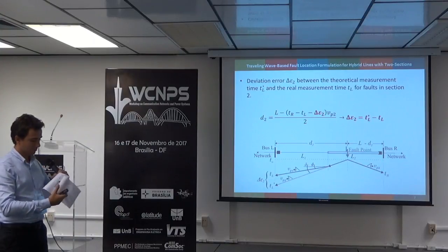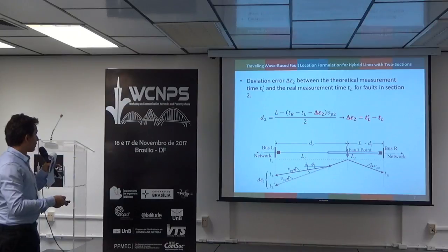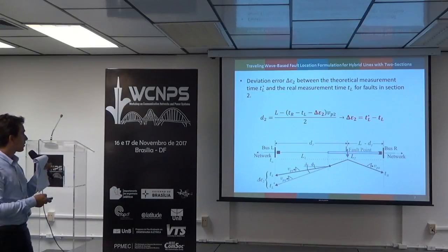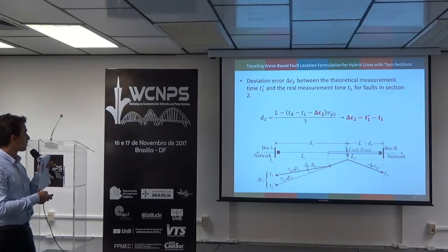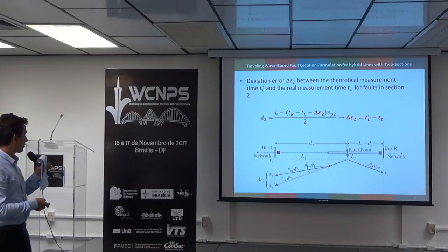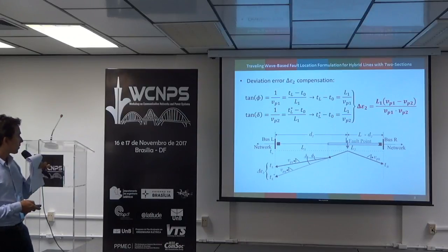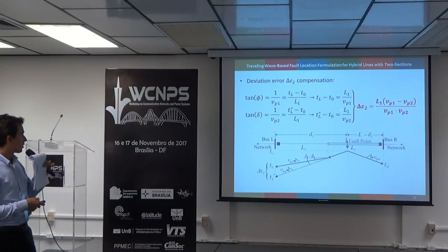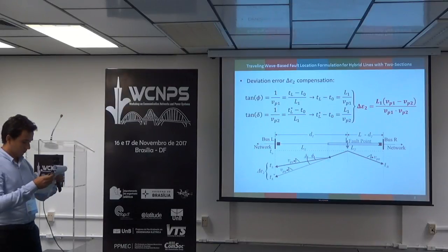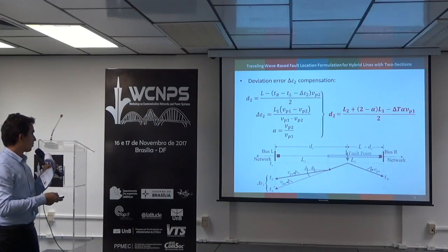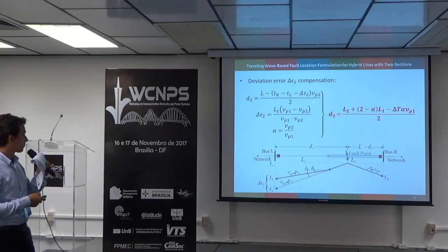So similarly, for faults in section 2, we apply the classical fault location method, and it's necessary to calculate the deviation error delta epsilon 2, illustrated here. Again, by the properties of similar triangles, we can obtain the deviation error for faults in section 2. And substituting this error in the classical formulation, we can obtain the second equation for fault location in section 2.